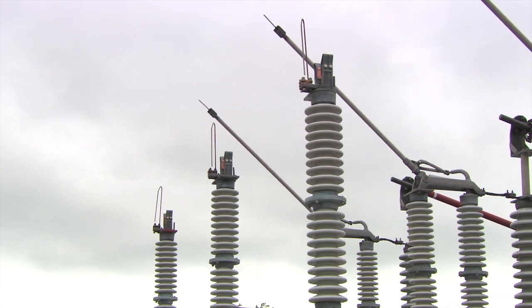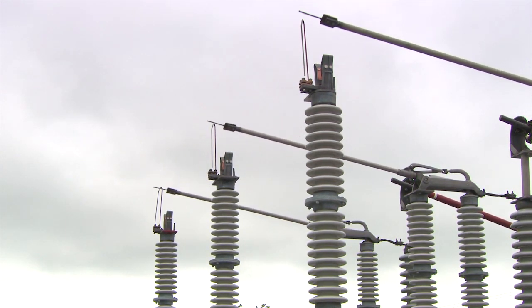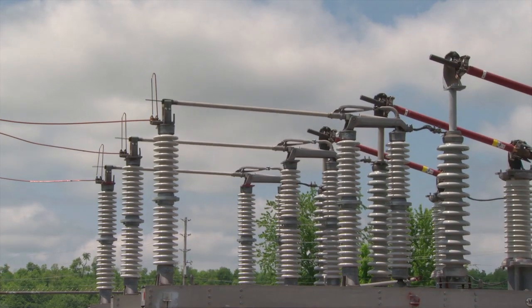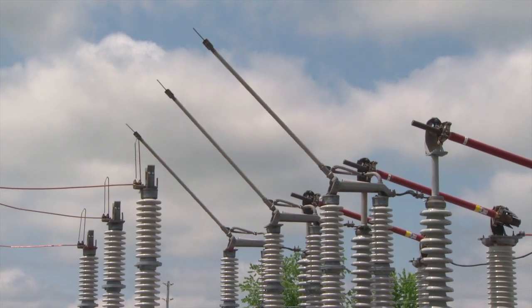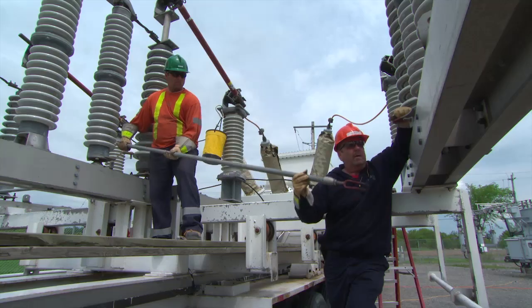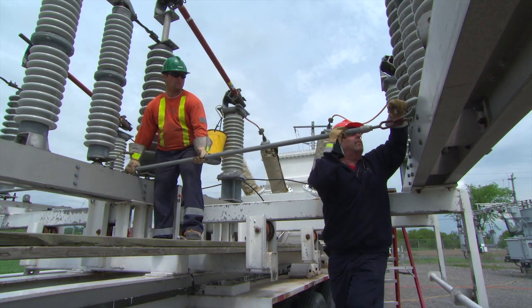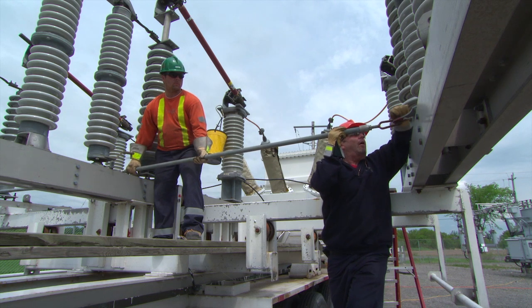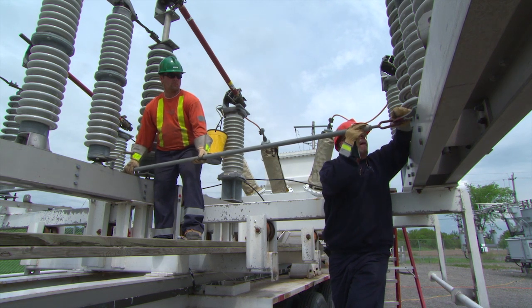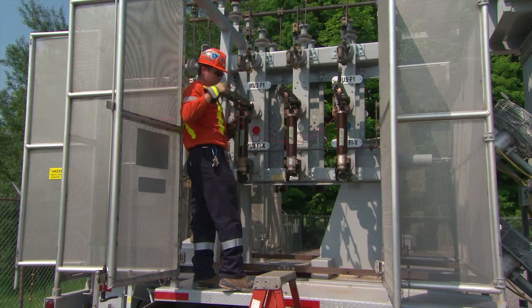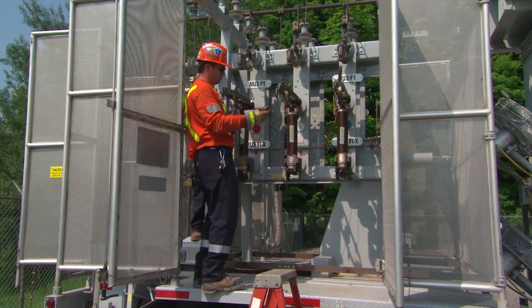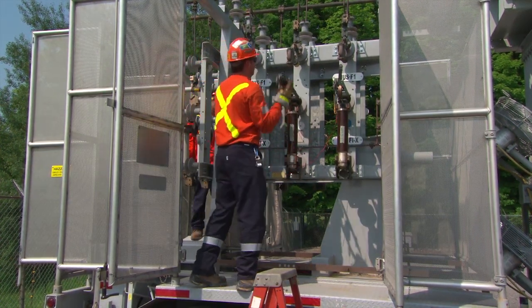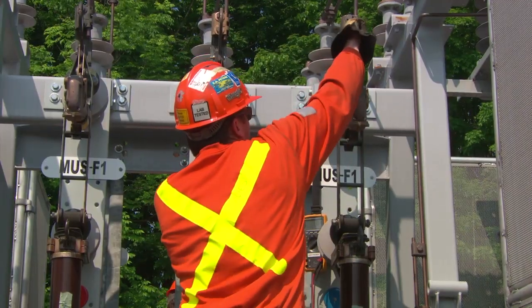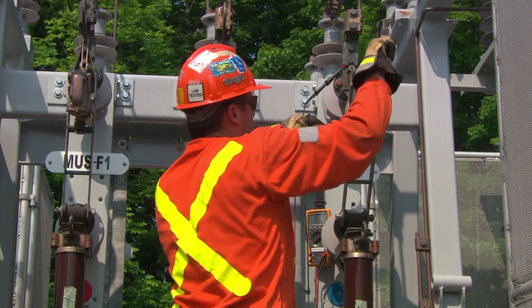Every mobile is equipped with 1 high-voltage switch. This switch is used to isolate or energize the main transformer of the MUS. On some mobiles, the operating rods are dismantled and stored for transport. Mobiles without reclosers are equipped with single-phase stick-operated feeder switches. These switches are used to pick up the station load.